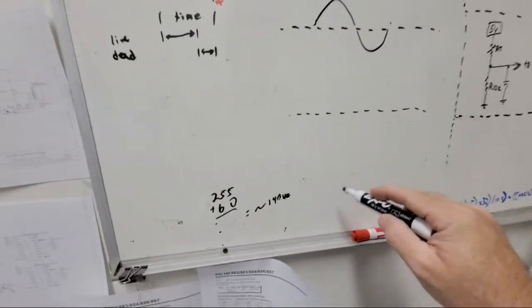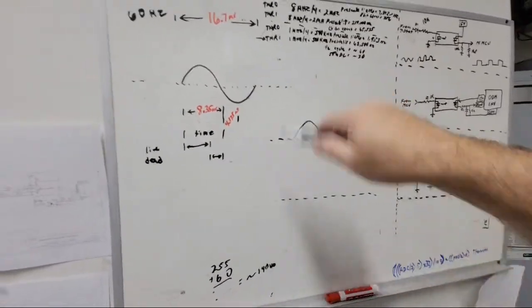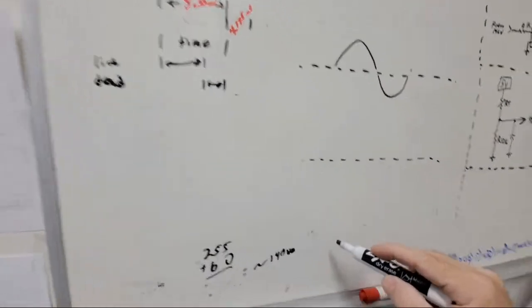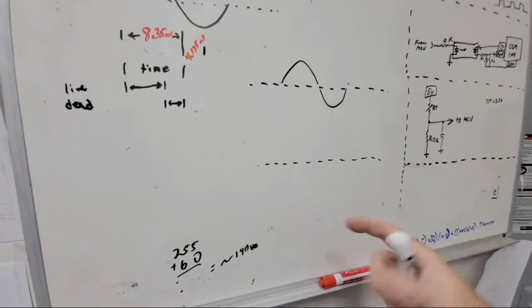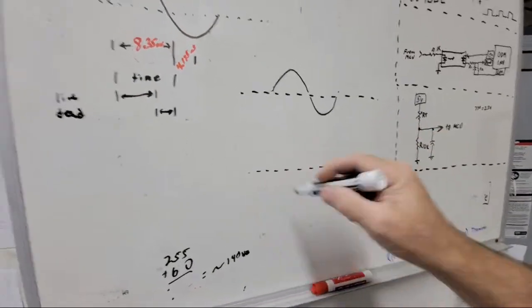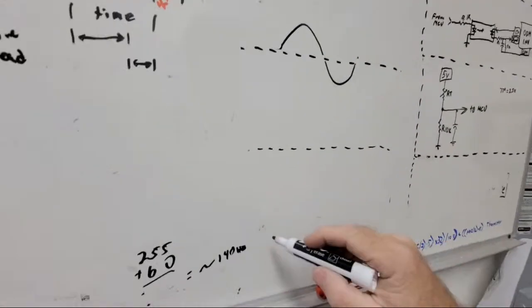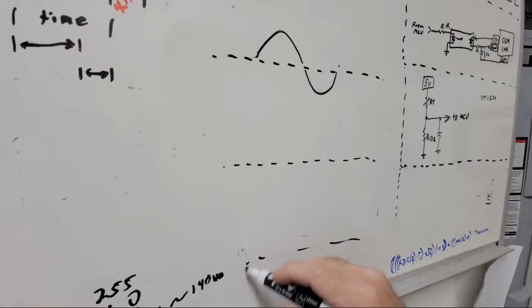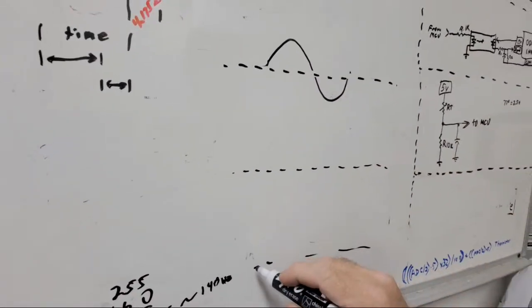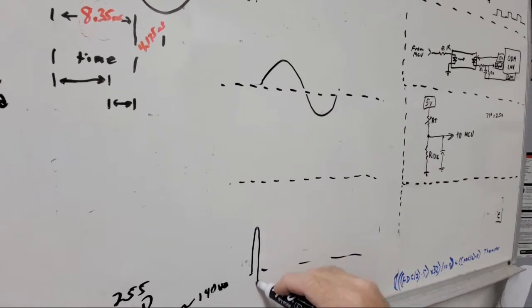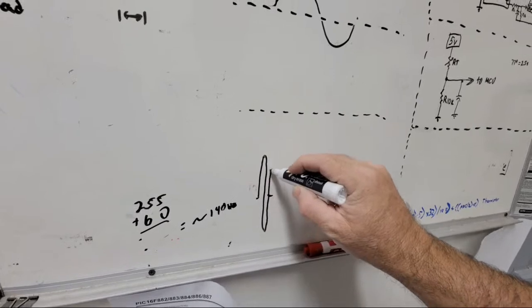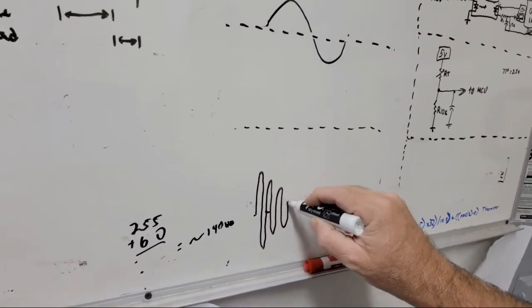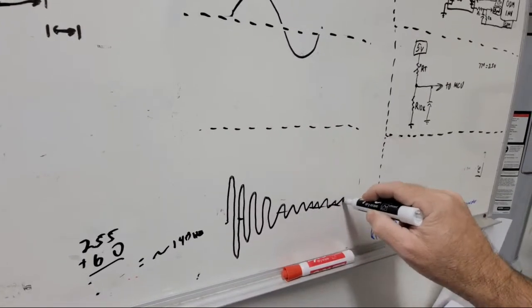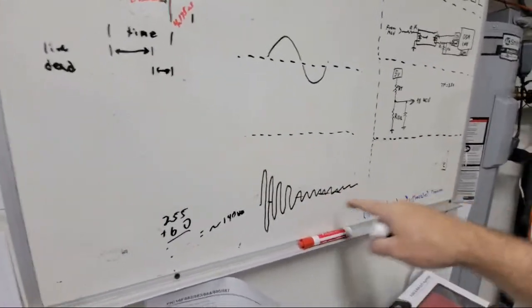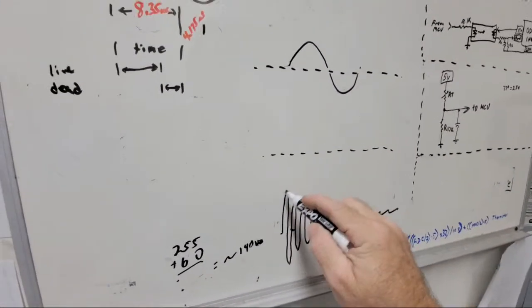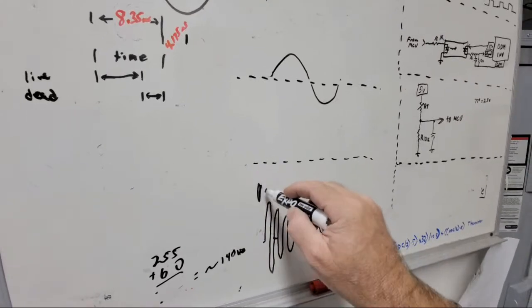But anyway, this is just one cycle, but if you have a bunch of cycles, 60 times a second, so when you first apply the voltage across the winding without any rotation, you just think of it as a long stretched out wire. Before the magnetic field comes on, your amps are going to follow, there might be some lag to the voltage, but it's going to go up to peak. You guys have all seen this before. This is just going to be crude, but as the speed of the compressor gets up, then you're going to just have your normal current following the AC sine wave. So this time here, like 1 second, is from here to way out here.